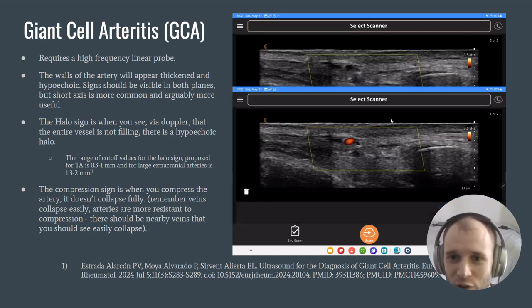Although with the higher frequency, you can look at how much higher resolution it is. Now, these arteries will be larger in someone with these issues. Just to give you a sense of scale here, this whole scale is 1.4 centimeters. This here is a little larger than 1 millimeter. So 0.3 millimeters would be at least half of this. If I try to compress this and only half of this compresses, that would meet the minimum criteria, right? This is a very small scale here, and look at the resolution, right? I could compress and see if that compresses or only compresses halfway. I could do that. So with 15 megahertz, I think this is plenty, and this is just a handheld ultrasound unit.